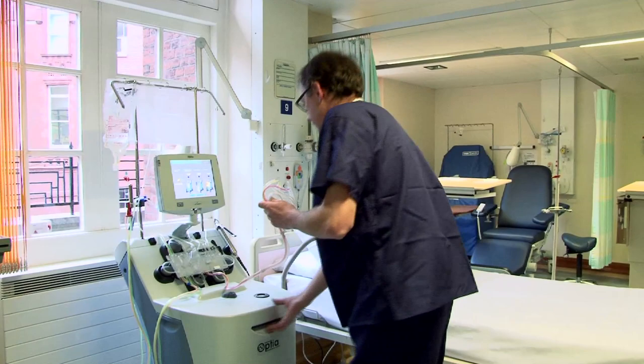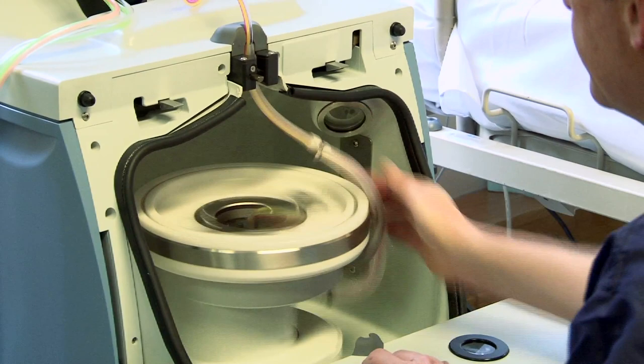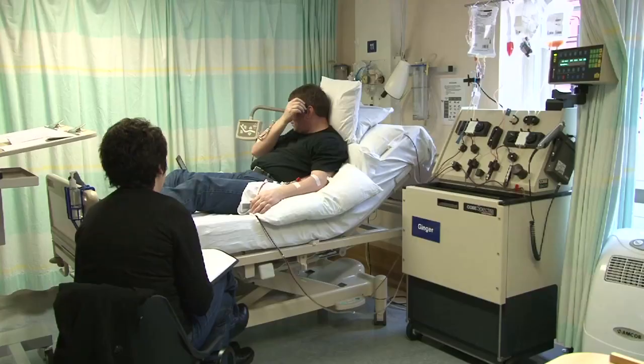This is an apheresis cell separator — it's the newest model of its kind on the market. What makes it special is that it has a camera within the centrifuge, which gives greater accuracy and efficiency and helps to identify cells more accurately when doing harvest or exchange procedures. At UCH, we currently have nine machines, one of which is the Optia. The other machines are the COBE Spectra — the oldest machines on the market. Although we have had them for a very long time, the company will no longer be able to support them. In the new cancer centre, we're also increasing our apheresis services from six beds to eight beds in the day unit.